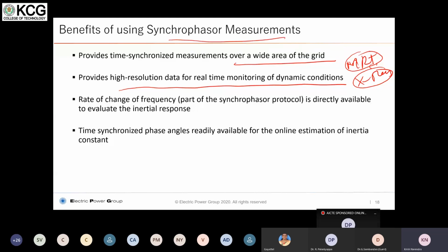And the rate of change of the frequency, which I told you the significance of, associated with inertia, is directly measurable from synchrophasor data. It comes as a quantity through the standard protocol itself. So it's available to you. And time synchronized phase angles are readily available for online estimation of inertia constant. So these are some of the benefits of using synchrophasor technology compared to the SCADA technology.